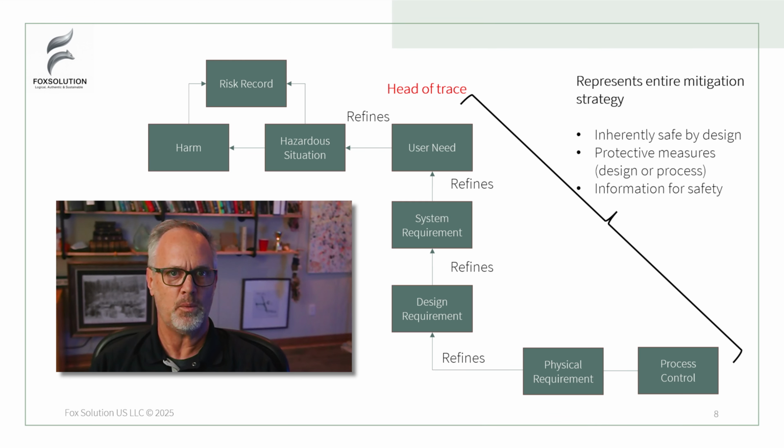So because of that, the risk record then carries the P2 factor. How often does it convert? And that is something that typically doesn't change regardless of what you're doing from a mitigation strategy. If I touch the wire and I expose myself to that electromagnetic energy, how often I get shocked or how often I fall over dead is not going to be different really based on my mitigation strategy. What I can do is reduce the P1 factor. So the mechanism by which that conductor becomes exposed, does it become exposed? What's the mechanism by which it does that? Those are the kind of things that I can mitigate, but not so much the conversion factor.